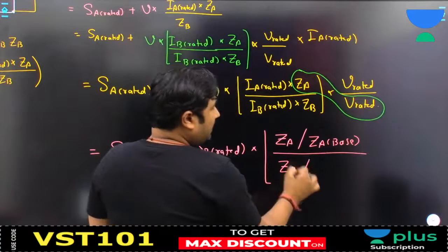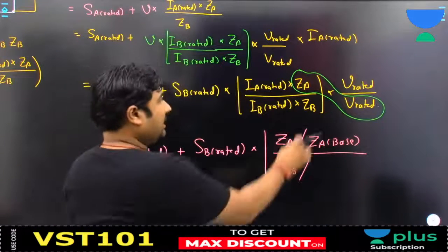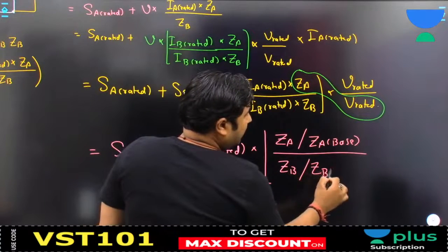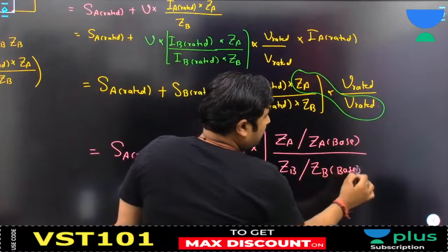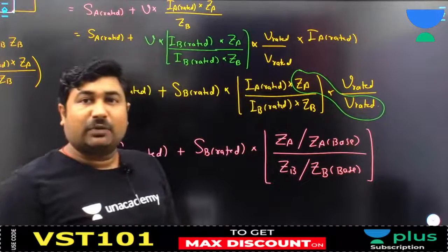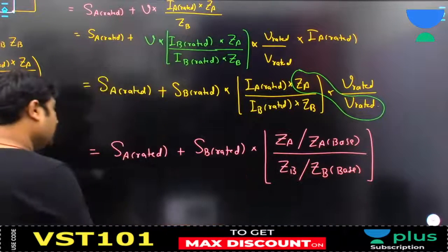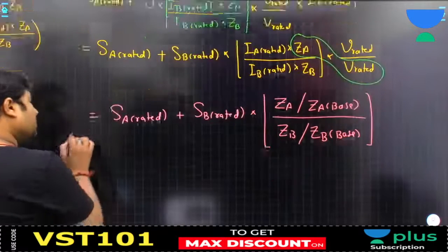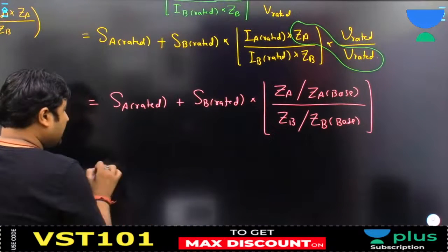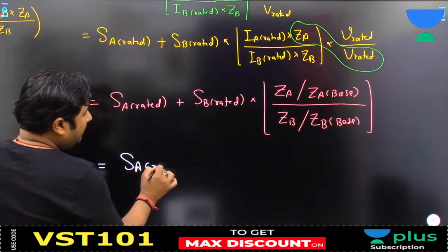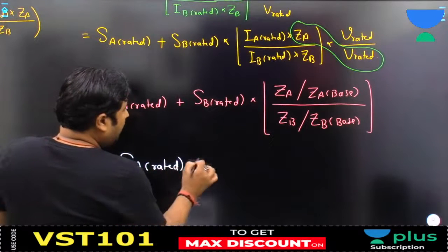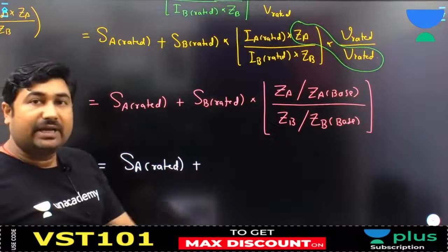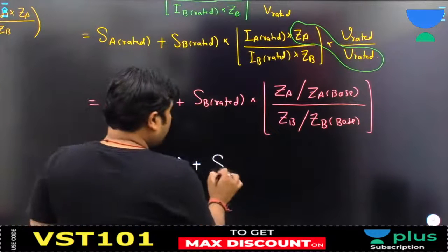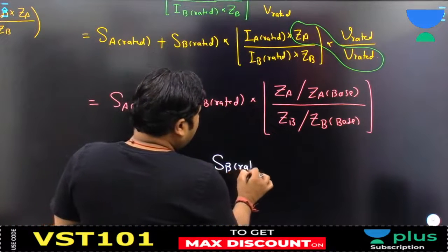Yes, sir. And ZB, which is in actual ohms, upon V rated by IB rated. V rated by IB rated is ZB base. So what is this? Actual impedance upon base impedance is per unit impedance. Wow, sir. So just by observing the nameplate, we are capable to identify the maximum kVA that can be handled by the two transformers going to operate in parallel.